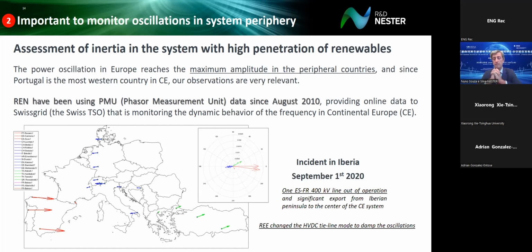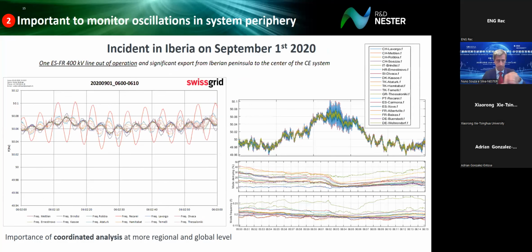In particular, with an incident two years ago, in September 2020, one of the lines between Spain and France went out of operation, causing a big impact on flows, reducing exports from the Iberian Peninsula. The Spanish operator was able to change the HVDC tie line modes to damp the oscillations, so it was controlled. But this shows the importance of coordinated analysis at a more regional and global level.